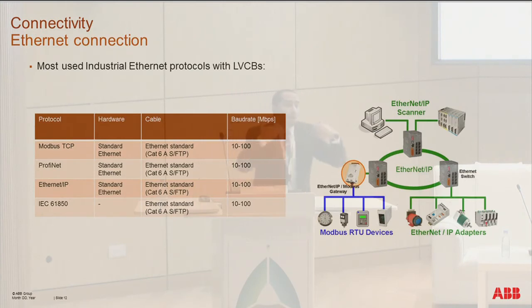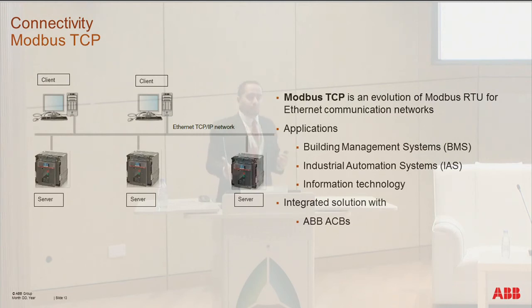So, in addition to the three protocols that we mentioned, now we have four protocols using Ethernet communication: Modbus TCP, Profinet, Ethernet IP, and IEC 61850. Modbus TCP is similar to Modbus RTU, I mean it's an evolution of Modbus RTU for Ethernet communication. It's also used for supervision of the system, with applications like BMS buildings. Modbus TCP is integrated in the ABB air circuit breaker EMAX2 without the need of any external converters, while the molded-case circuit breakers only need an external converter, which we can provide.